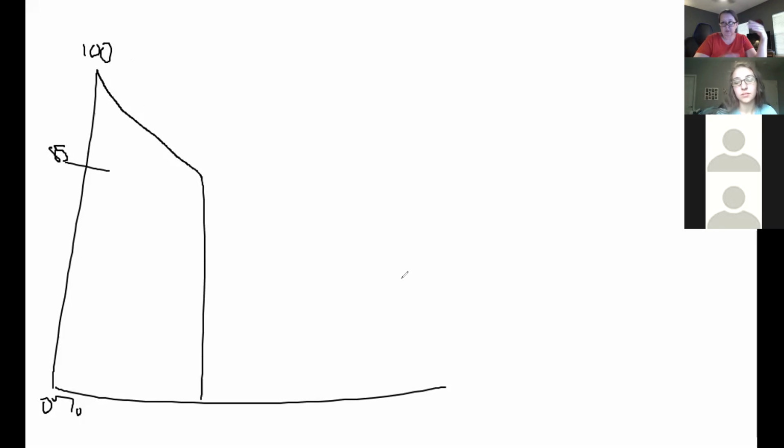So you expect, okay, it's 85, 80, 74, 70, 62. It's pretty much like 85 and then it drops off a cliff. So this is why when we are troubleshooting and we're getting in the 90s and the 85s, we really have to do something about it.